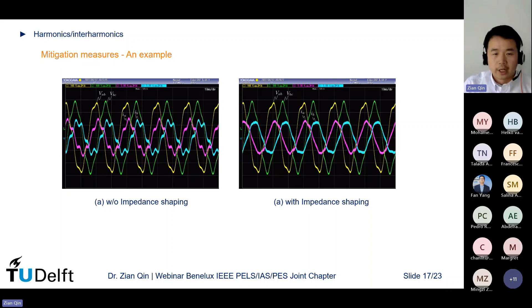So what is impedance shaping? As I mentioned, the impedance of the charger is affected by the power filter, but it's also affected by the control. You do not often or easily change the power filter of your charger, but you can easily change the control. So impedance shaping is actually kind of a control tuning, but you look at it from the impedance perspective so that you can do the fine tuning easier. That's the idea.